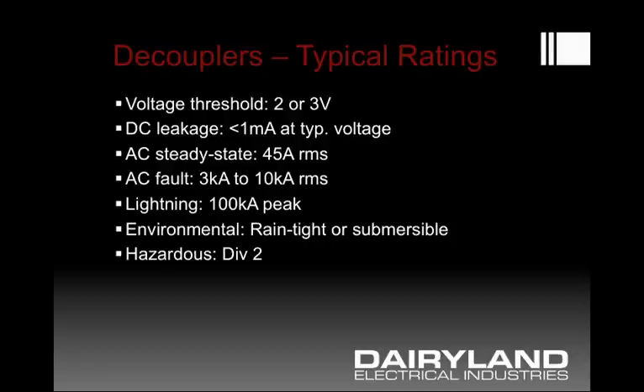Lightning current ratings can very commonly be 75 or 100 kA as the peak value. Devices are commonly rain tight or submersible depending on where the product is located, either of which could apply. The most common hazardous location is generally classified as division two, though there are some division one locations where hazardous gases are expected to be present all of the time, but that doesn't tend to be the majority of sites.